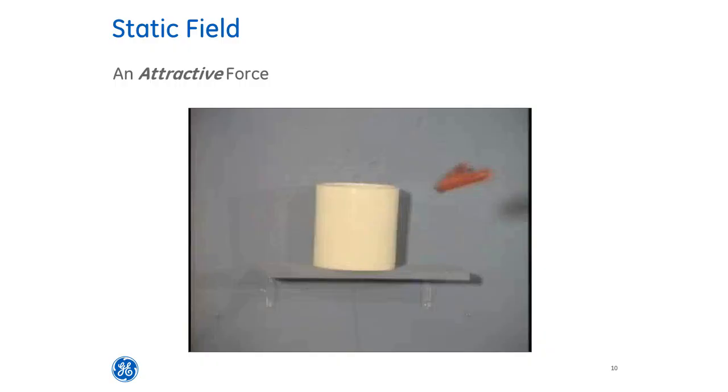The missile effect refers to the capability of the fringe field of the static magnetic field of an MR system to attract a ferromagnetic object and draw it rapidly into the scanner with considerable force. That was a fairly short recording, but it was an impactful one. Imagine if it was a person instead of those bricks in front of the magnet.